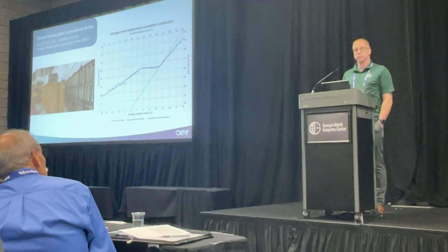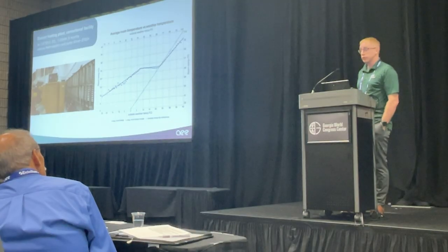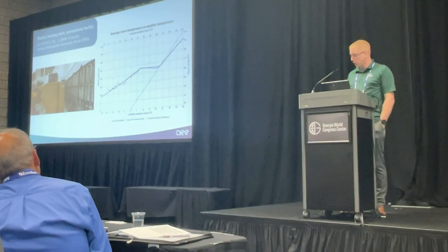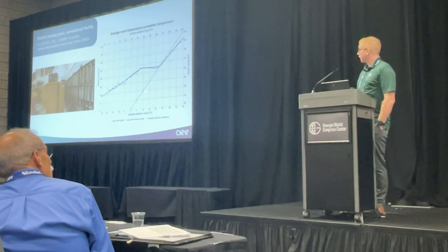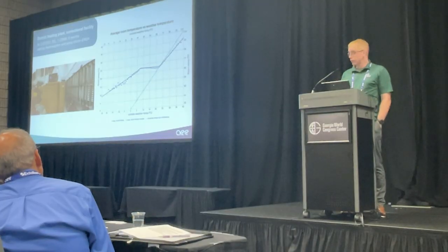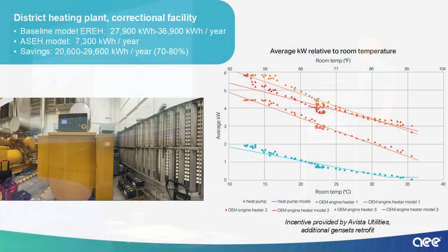They also had heating because they are a steam plant, so they don't care. They did provide some heating, which you can see essentially maintained the temperature, until the losses from the room were greater than the amount of heating that could be provided. I will say that the green line here is the weather temperature, so you can see how the room temperature changed relative to weather temperature. So you can see the variation in the 3 different baseline gensets.